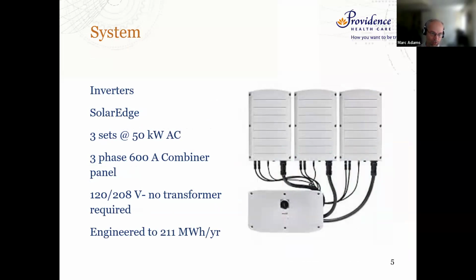The inverters themselves are made by SolarEdge. We have 3 sets of 50 kilowatt, 3-phase AC converters. These go into a 600 amp combiner panel that feeds down into our switchgear. The inverters sample the incoming power from the grid and adjust the phase and voltage to adapt to it, so everything operates at 120/208 volt power — there's no transformer required, which helps reduce a step in the chain.